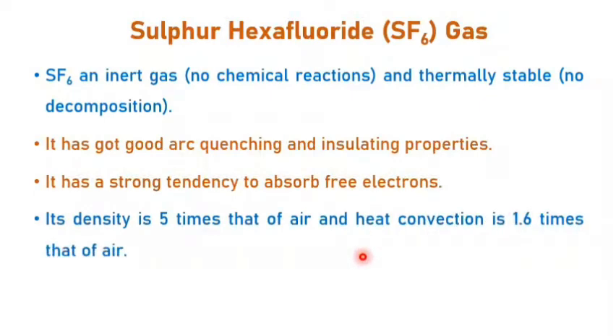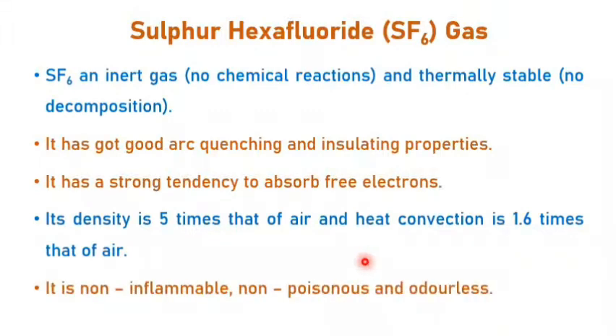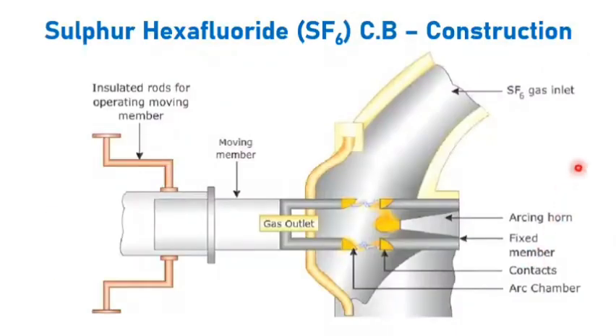density is 5 times that of air and its heat conduction is 1.6 times that of air. Compared to air, it can conduct the heat very fast. It is also non-inflammable, non-poisonous and odorless. So these are the properties that make it suitable for arc quenching in circuit breakers. Let us see the construction of the SF6 circuit breaker.